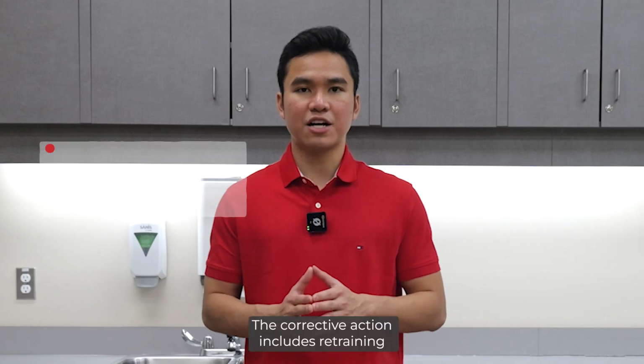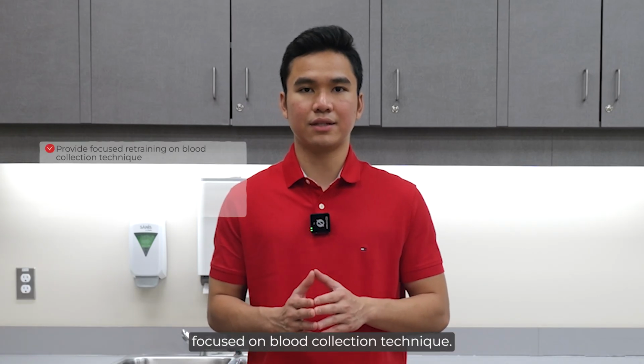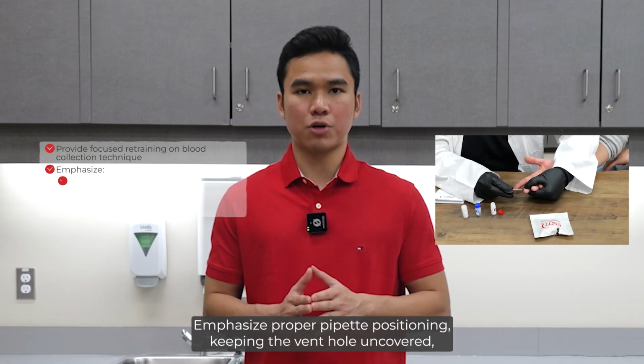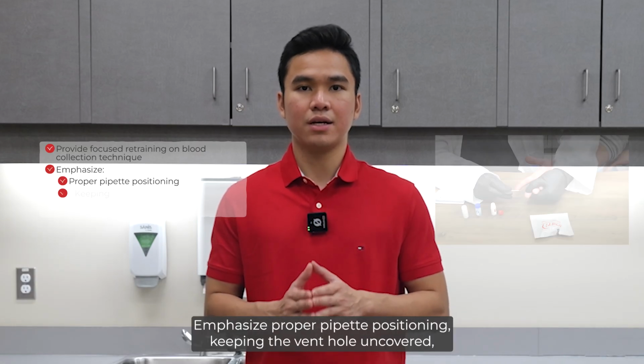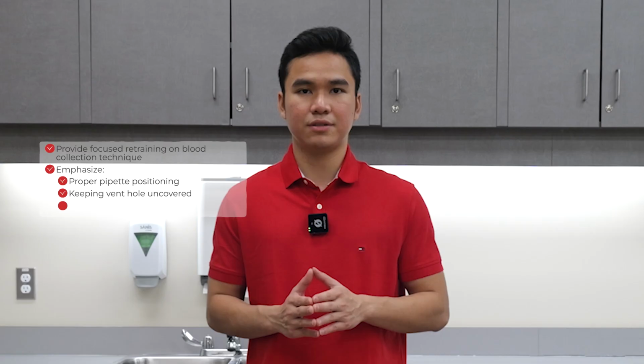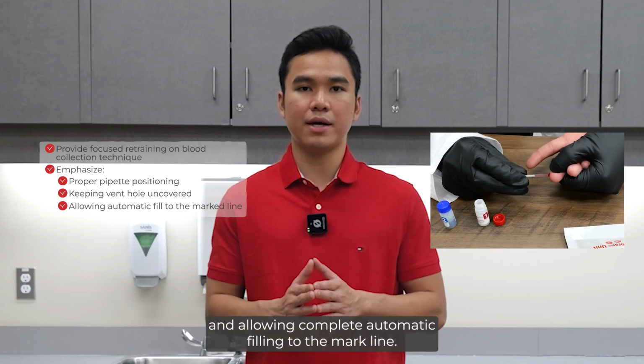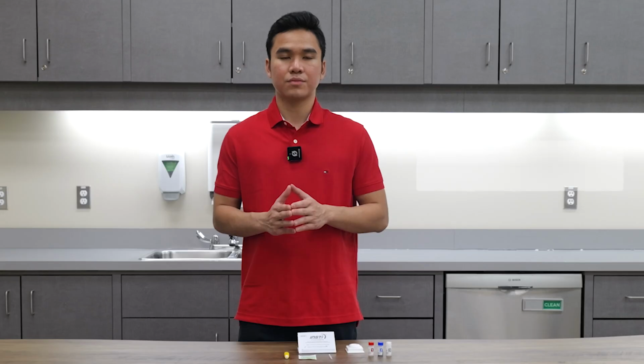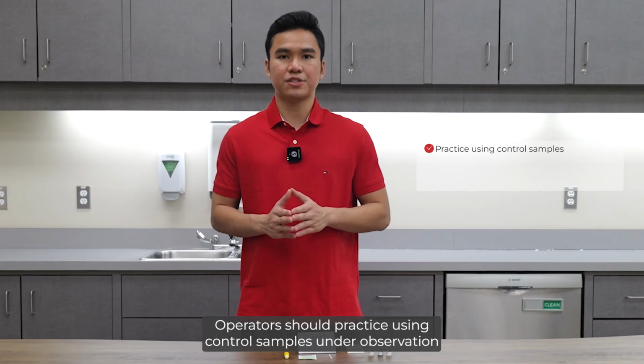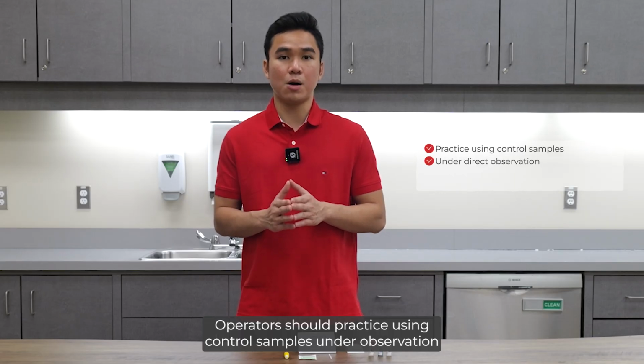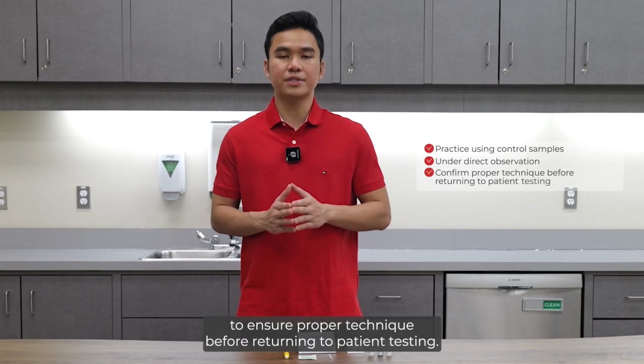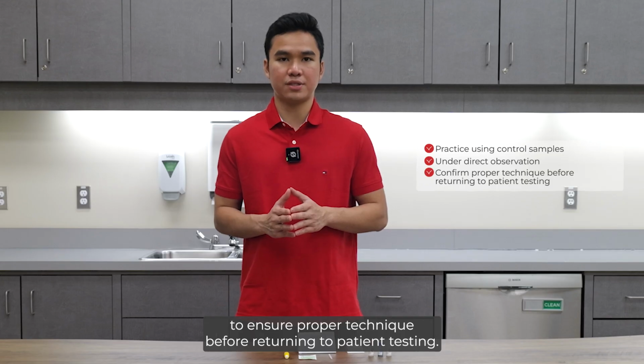The corrective action includes retraining, with focus on blood collection technique. Emphasize proper pipette positioning, keeping the vent hole uncovered, and allowing complete automatic filling to the marked line. Operators should practice using control samples under observation to ensure proper technique before returning to patient testing.